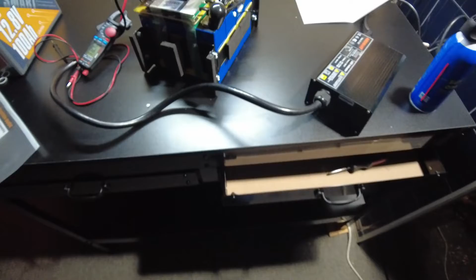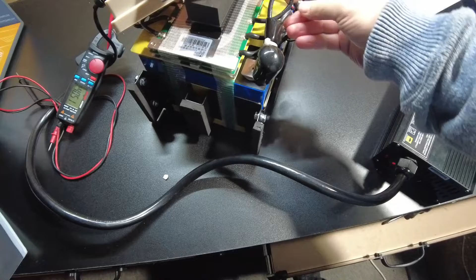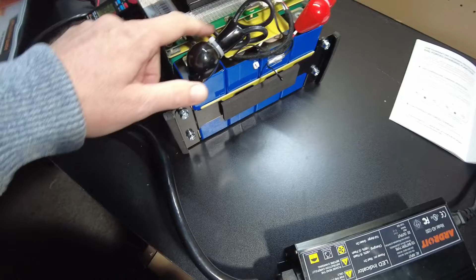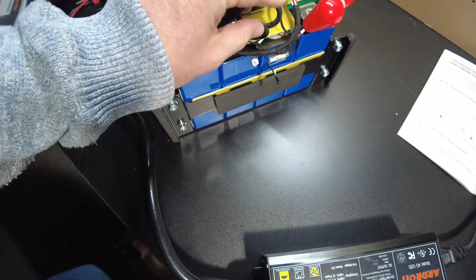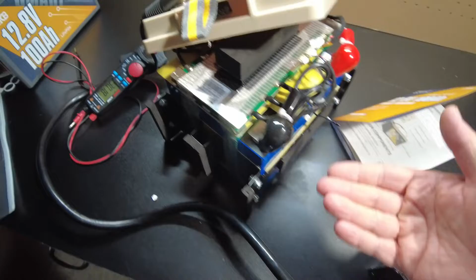Okay, so the only thing left I want to do is hook up the inverter and pull over 100 amps. I want to verify that these cables are not getting too hot. Normally, 3 10 gauge cables would be good for 90 amps, and this battery says you can continuously discharge at 100 amps. So we're going to test this and make sure nothing is getting overly hot at 100 amps. I kind of don't think it will, but we're going to check it anyway. Let me hook that up and I'll be back.